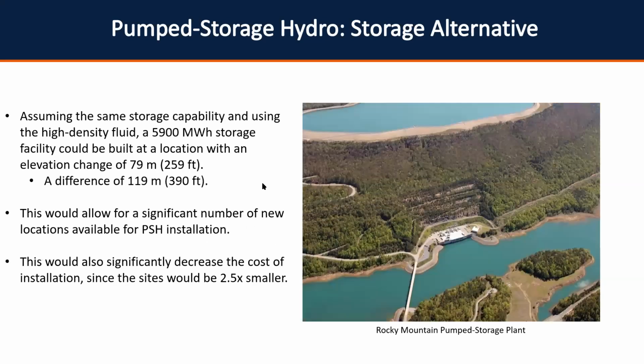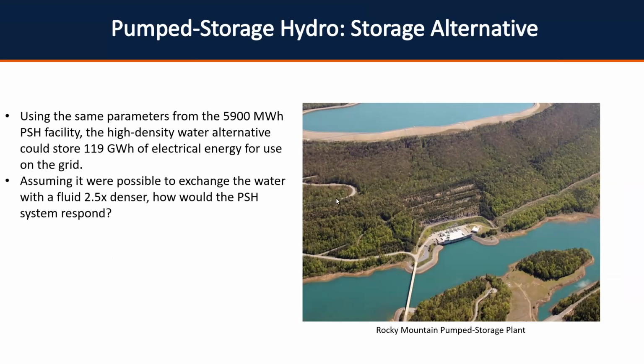If we assume the same volume of storage, we could put that same 5,900 megawatt hour storage facility at a location with a height of 259 feet, which I think is like a small hill, or maybe a large hill. That's like 400 feet of difference. That's going to open up a lot of new pump storage sites. It should also decrease the cost. By how much, I think it's definitely worth investigating, but presumably these things will be smaller than what we have now. Alternatively, if we retrofit, so this is Rocky Mountain Pump Storage Facility. This is one of ours.